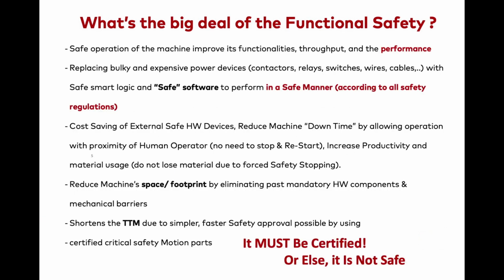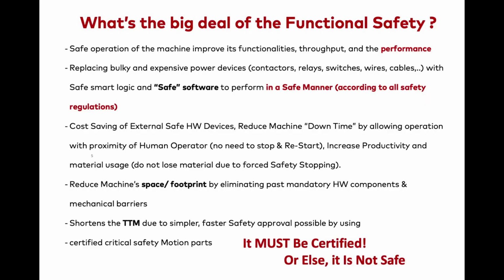So what is the big deal with functional safety? With functional safety, you are able to reach safe operation of your machine and improve its functionality. Throughput is increased and performance is enhanced. Functional safety replaces bulky and expensive power devices which were used in previous generations before functional safety was introduced into motion drives. You remove the need for contactors, relays, and special expensive hardware with safe smart logic implemented inside the servo drive by software in a safe manner according to all the safety regulations. Cost saving is a significant point for the machine builder.